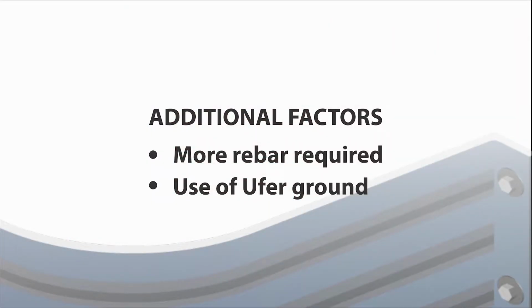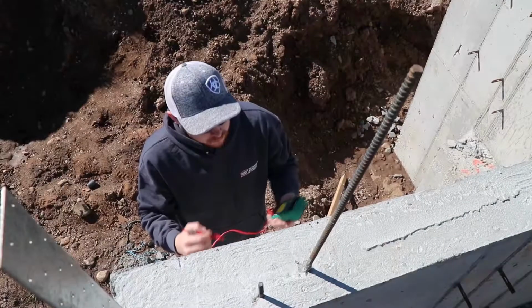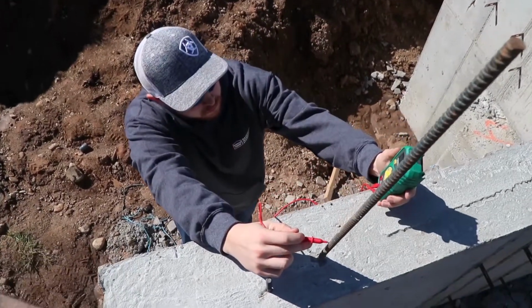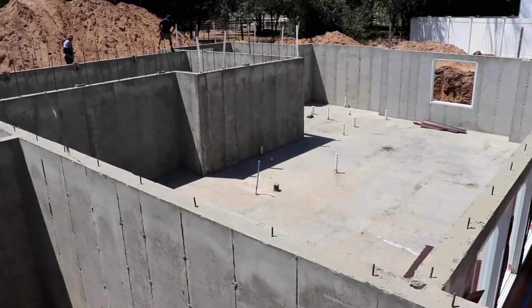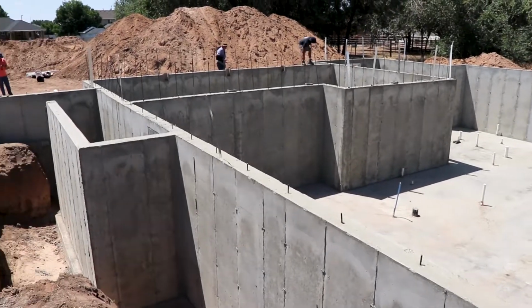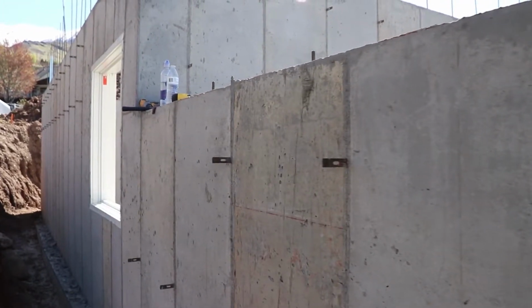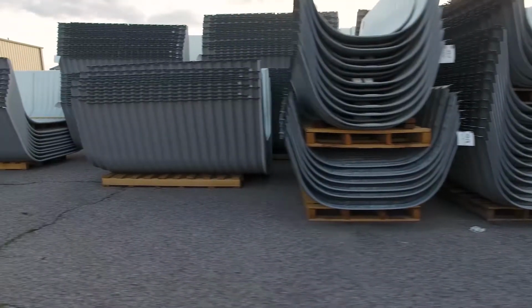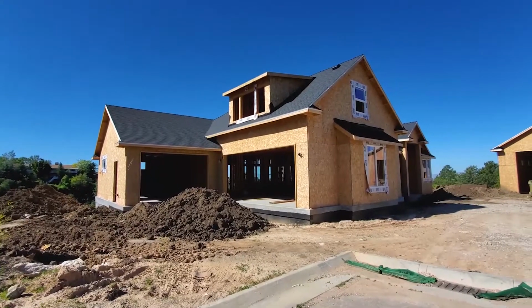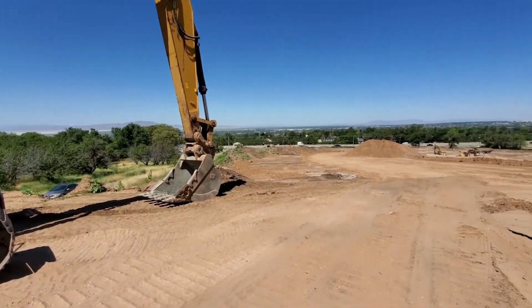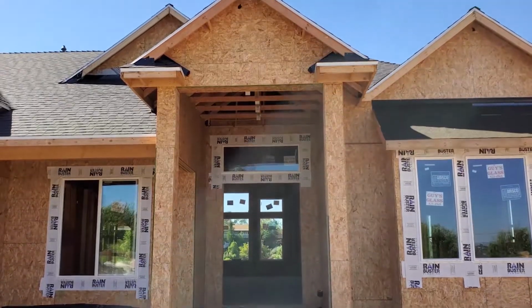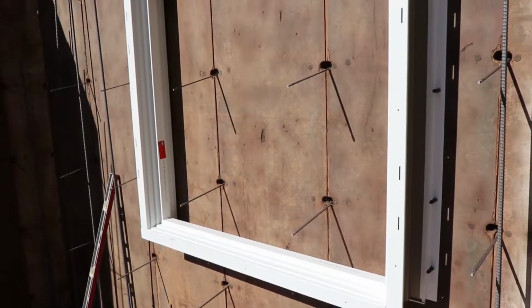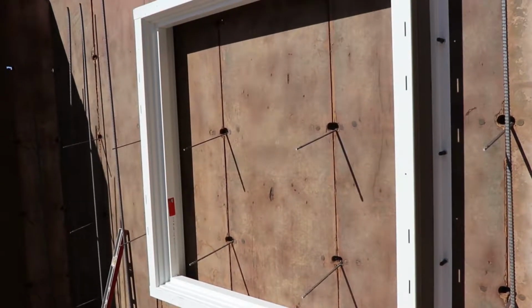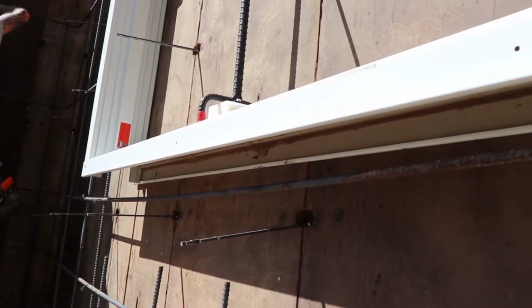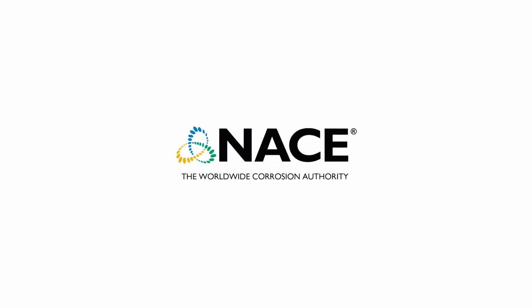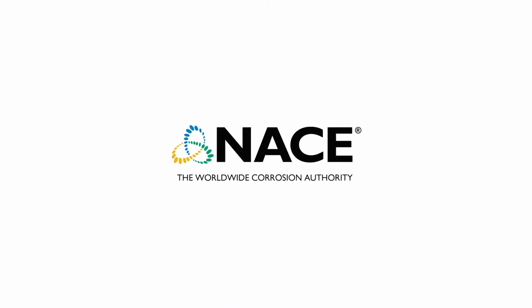Second, Ufer ground. The introduction to the electrical code of the use of Ufer ground, which grounds the electrical system to the rebar in the foundation. The Ufer ground and network of rebar function as an electrical conductor. These changes in home building practices have an impact individually and together. Corrosion's research helped us to identify exactly what was causing the window wells to corrode. Their subsequent recommendations are based on standards set by the National Association of Corrosion Engineers.